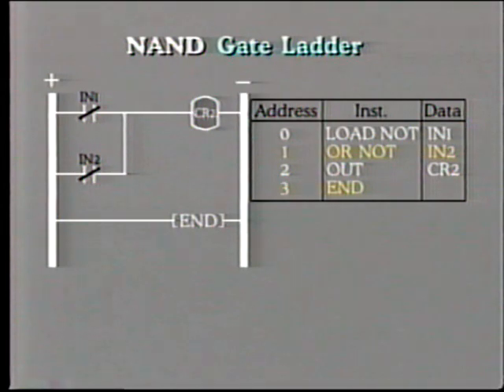Further examples of multiple block operation are included in your workbook to allow you more time to study these in detail. Here is the logic arrangement for a NAND circuit using normally closed input contacts IN1 and IN2. When there is no input to points IN1 and IN2, the output control relay is energized. With an input signal on either point, its contact will open, but the control relay will continue to be energized via the other contact. However, with an input signal on both points, IN1 and IN2, both contacts will be opened and the output will be de-energized. The ladder coding instructions are shown here.